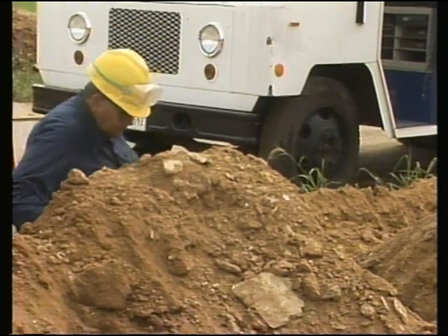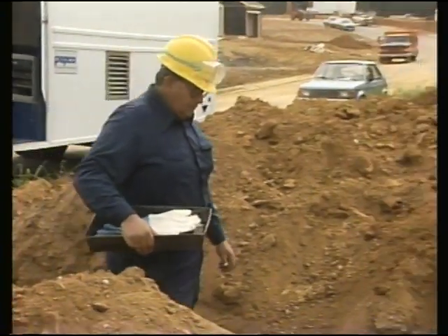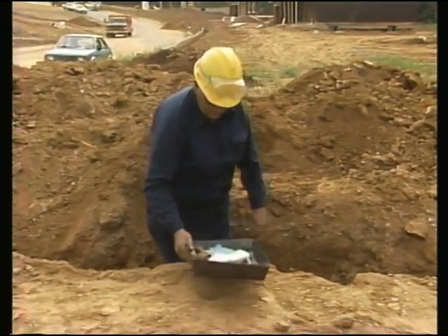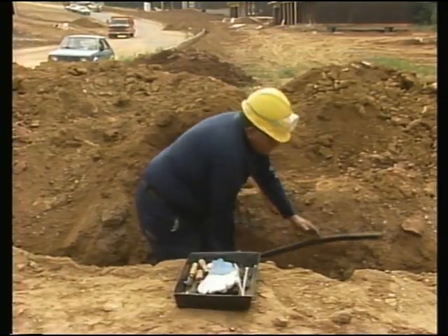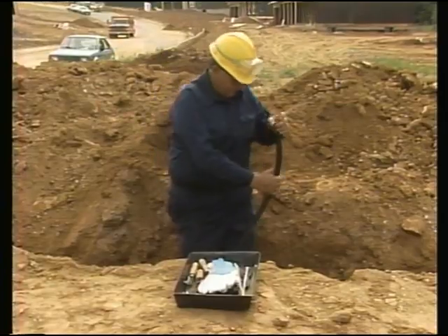To see how a cable is prepared for splicing, we'll watch this workman as he prepares a single conductor primary URD cable for a tape splice. All of the necessary procedures have already been followed for de-energizing, grounding, and testing the cable for dead. Keep in mind that the directions we'll see the workman following are for the specific type of splice he's preparing.